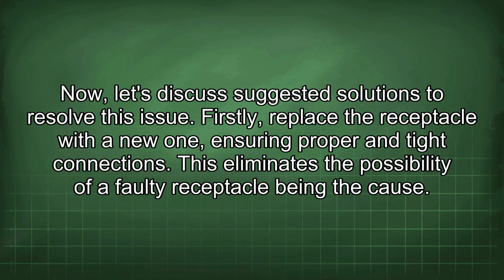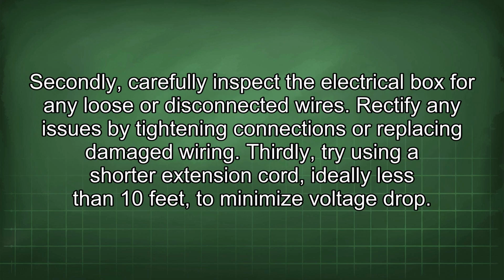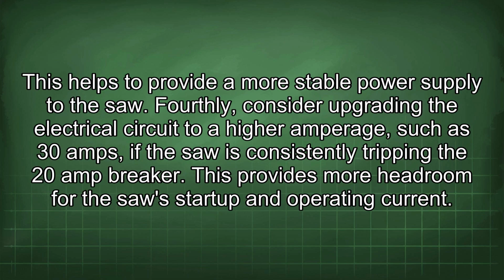Firstly, replace the receptacle with a new one, ensuring proper and tight connections. This eliminates the possibility of a faulty receptacle being the cause. Secondly, carefully inspect the electrical box for any loose or disconnected wires. Rectify any issues by tightening connections or replacing damaged wiring. Thirdly, try using a shorter extension cord, ideally less than 10 feet, to minimize voltage drop. This helps to provide a more stable power supply to the saw.